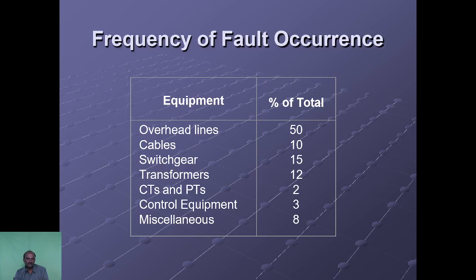Each equipment is affected by fault occurrences. Overhead lines are mainly affected, with 50% of the fault occurrences. On cables it is only 10%, switchgear 15%, transformers about 12%. CTs and PTs are affected by only 2%. Control equipment is 3%, others are about 8%. So the main component which is frequently affected by the fault is the overhead lines.